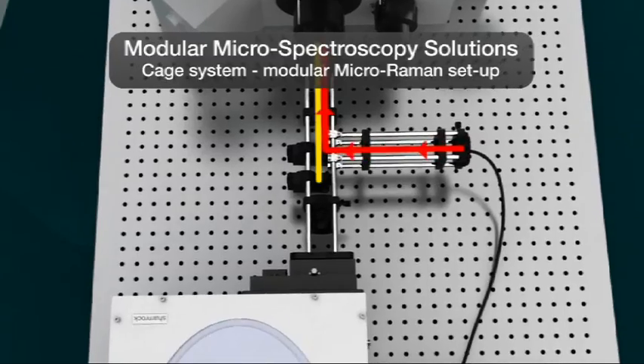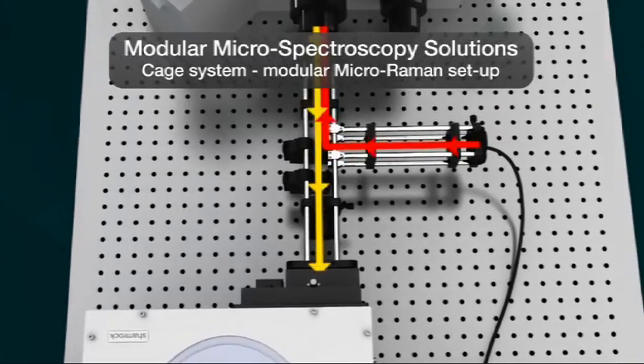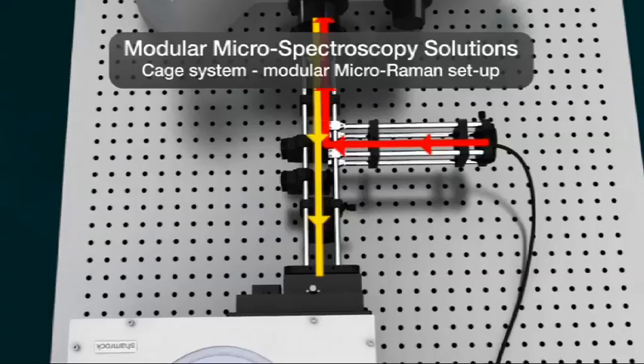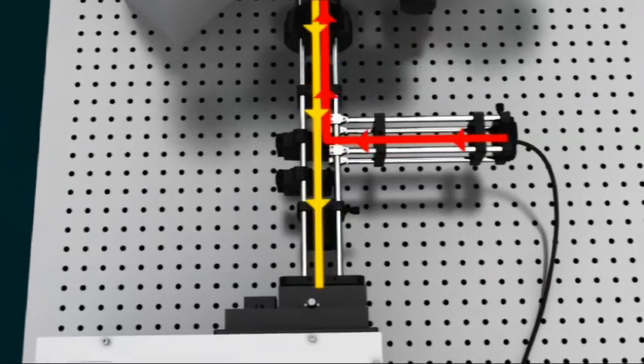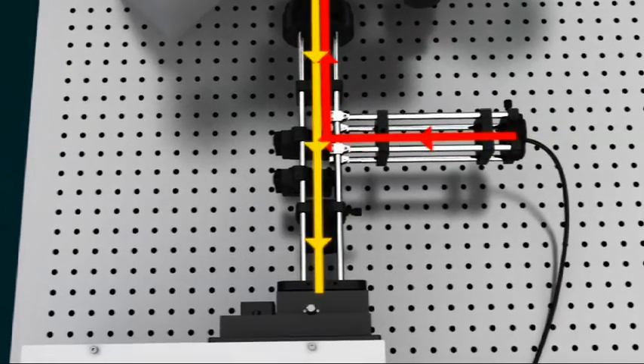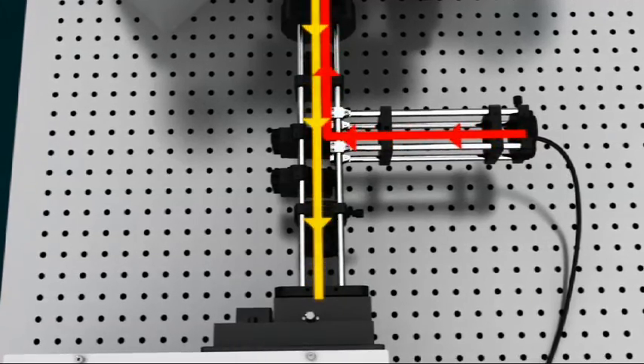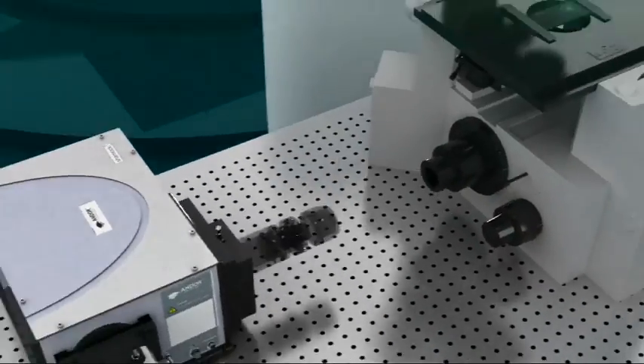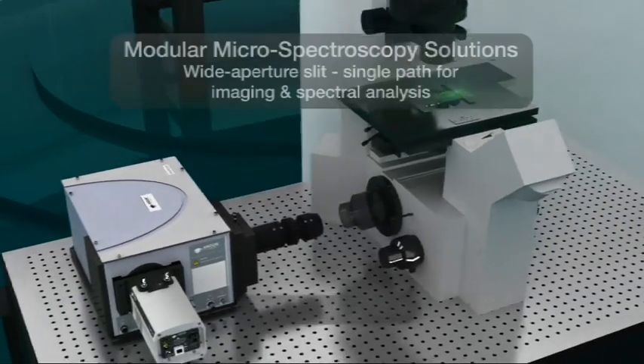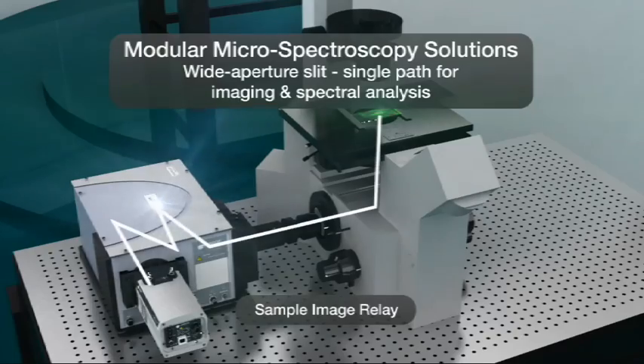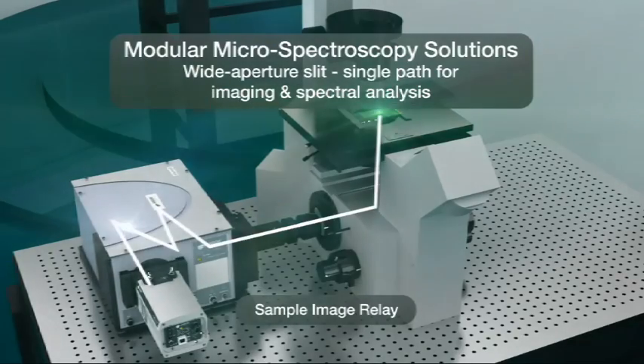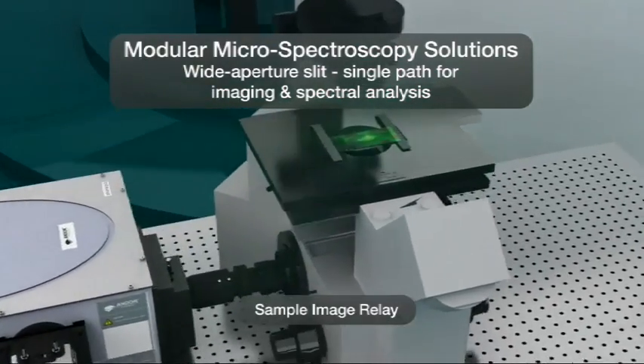But all these setups need two separate detectors for imaging the sample on one hand and carrying out the spectral analysis on the other hand. The solution is to enable the spectrograph to relay not only the spectral information, but also the microscope sample image with a sufficiently large and aberration-free field of view.